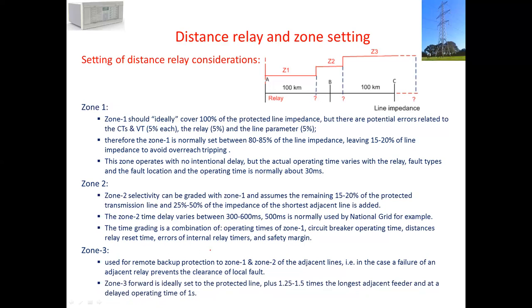Zone 3 is used for backup protection, but it's provided at an operation after delay time or longer time. Ideally we expect the fault to be covered by zone 1 or zone 2, but if not, zone 3 will provide the backup. The zone 3 setting is 100% of the protected line plus the next line plus 25% to 50% of the third line, or 1.25 to 1.5 times the longest adjacent feeder.